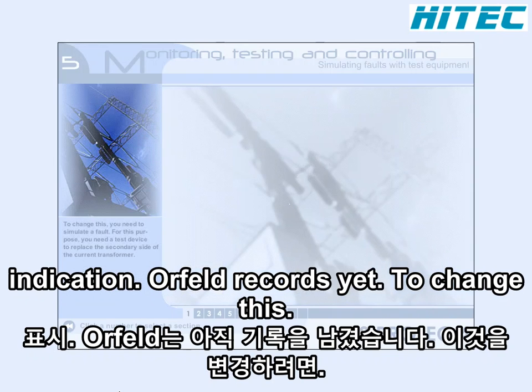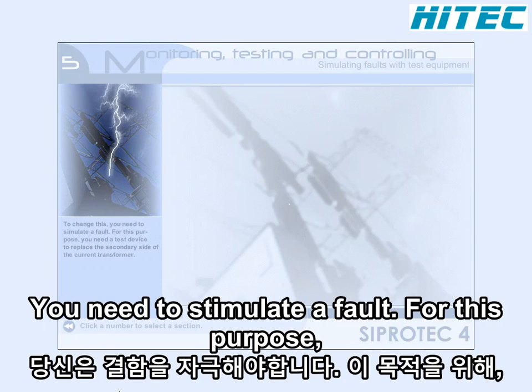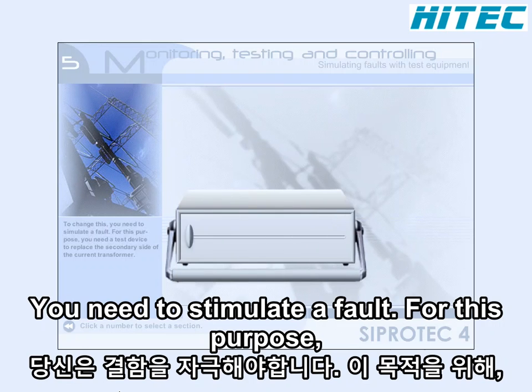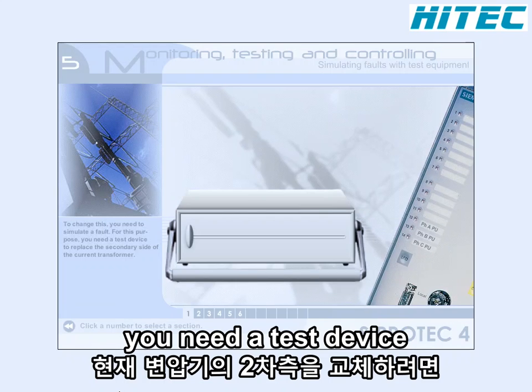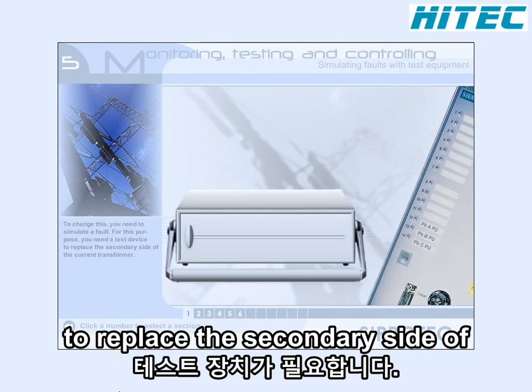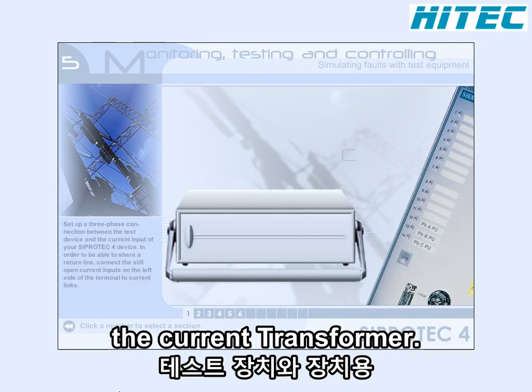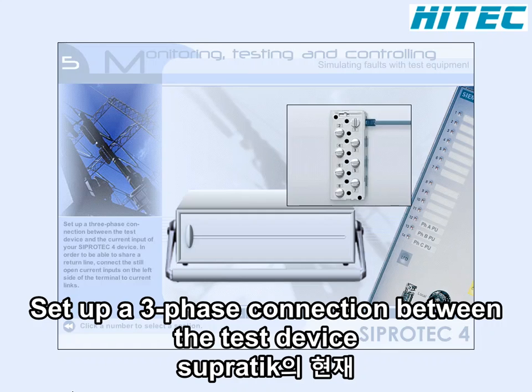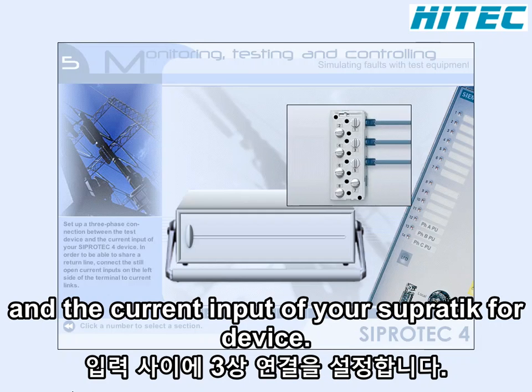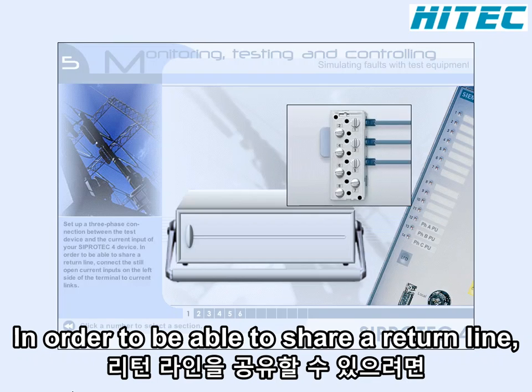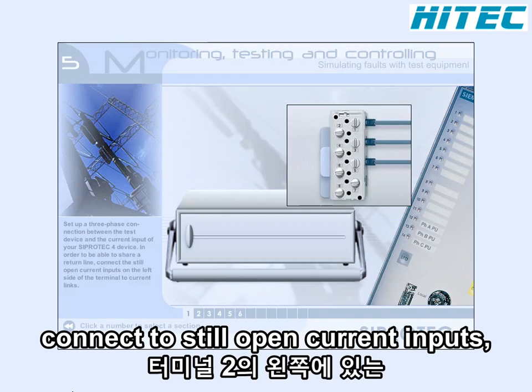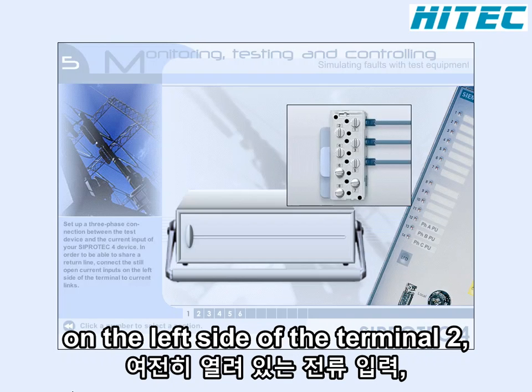To change this, you need to simulate a fault. For this purpose, you need a test device to replace the secondary side of the current transformer. Set up a 3-phase connection between the test device and the current input of your SIPROTEC 4 device. In order to be able to share a return line, connect the still open current inputs on the left side of the terminal to current links.